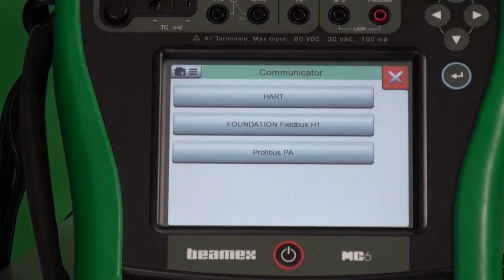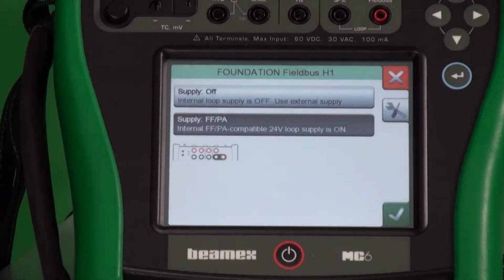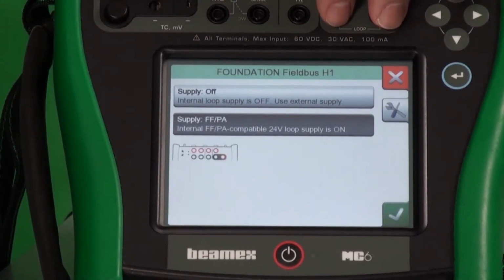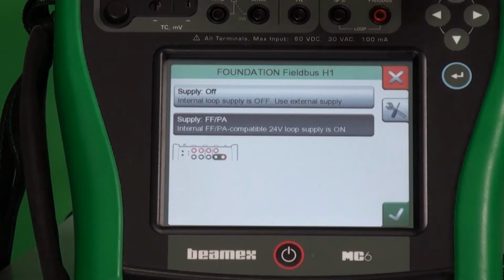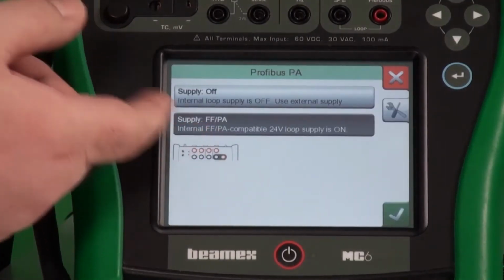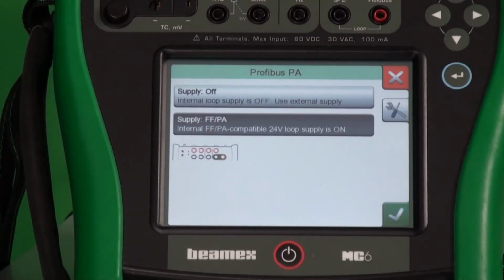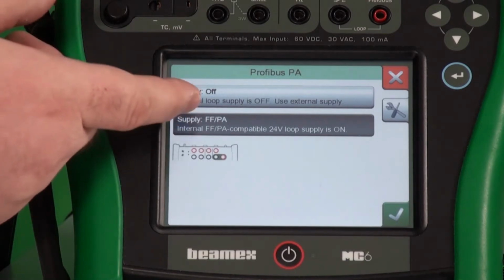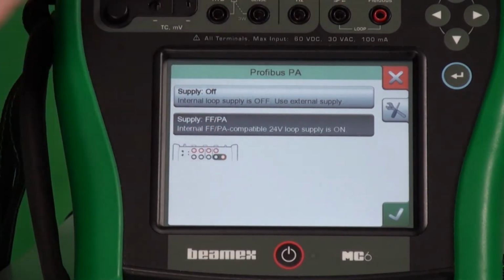Let me back up. Also, Foundation Fieldbus, it's the same thing. The same two connections. You decide whether or not you have loop power. Now, one thing I didn't mention with HART is that we build in the 250 ohm resistor for that communication. In Foundation Fieldbus, it's a 50 ohm communicator. So by using supply on, we automatically put that in. If we go back to Profibus, same thing. Profibus also uses a 50 ohm resistance. Supply on, same two connections.